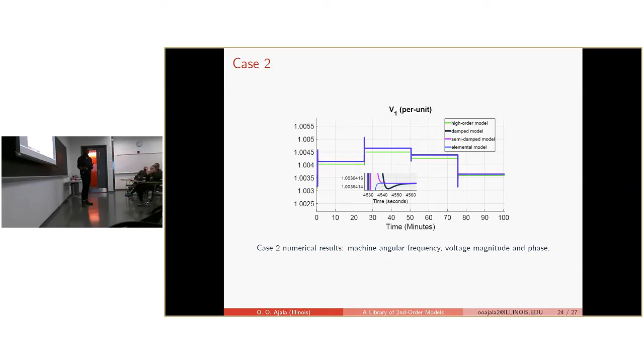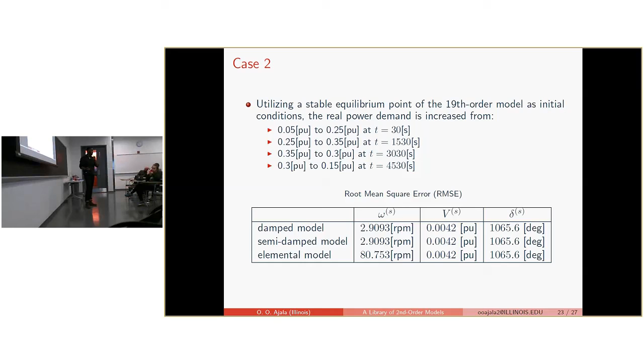And the angle. So we took it a step further and we computed the root mean square error for all these models. If you look closely, for the angle and the voltage, they're very close—the first order approximation doesn't change much. But for the frequency, we see that the error for these two models is significantly less than that of the elemental model. We can explain this because these models are taking into account the effect of the damper windings.